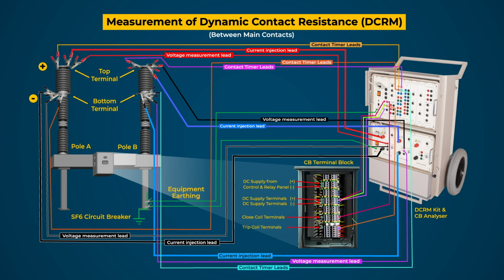Connect contact timing leads to the breaker terminals. Do the internal connections between the DCRM kit and CB analyzer kit and connect single phase 230 volt AC supply to both kits. Check all the connections and the setup is ready to perform the test.